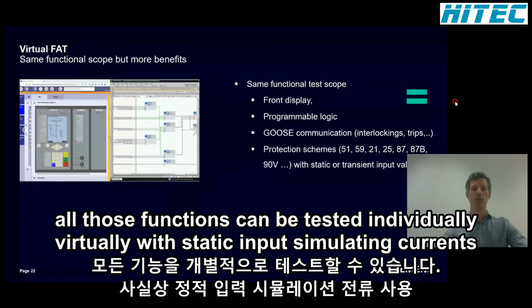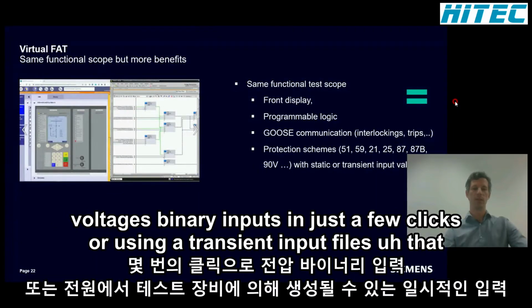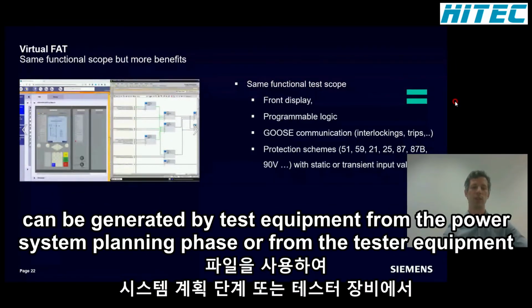All those functions can be tested individually and virtually, with static inputs simulating currents, voltages, and binary inputs in just a few clicks, or using transient input files generated by test equipment from the power system planning phase or from the test equipment itself.